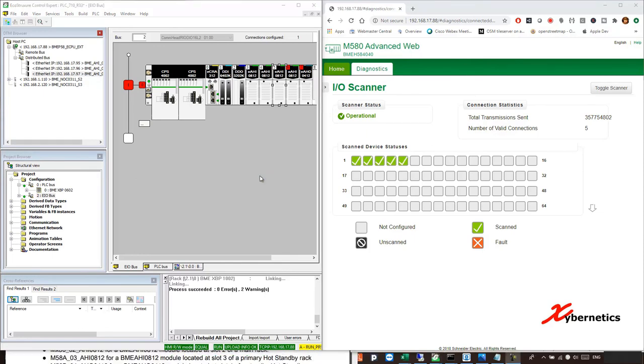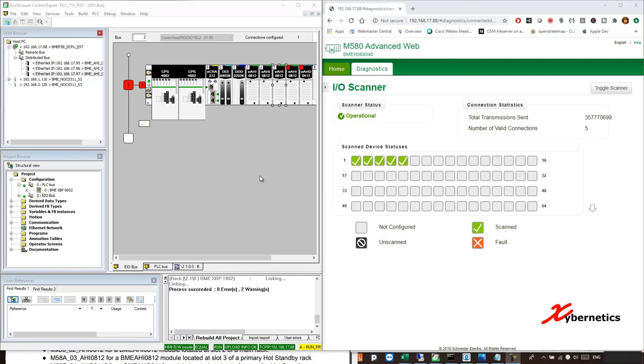Before I close this tutorial, I want to mention a few things. First of all, if you are only planning to use 4 to 20 milliamps and there's no plan in your horizon to use HART, stick with the AI card that only serves 4 to 20 milliamps, which is BMX AMI 0810. But if you have plans to put HART, sure, put AHI itself. The reason behind that is that the AHI is a bit tedious. In terms of configuration, you have to make sure that you don't forget to disable the HART. In an event that you need to enable the HART, you have to backpedal and enable that HART, like what I showed you just now. That's a bit difficult to configure, convoluted or tricky to configure. Second is cost. AHI is naturally more expensive than AMI, which is 4 to 20 milliamps only.